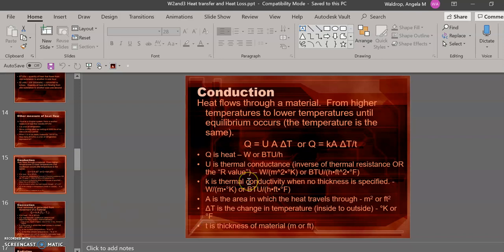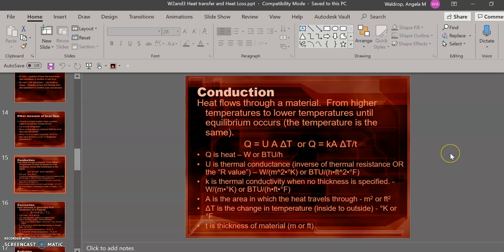For the first mode of heat transfer, conduction, here's the equation needed to do calculations. You will notice that there are two equations here. The first one, Q equals UA delta T, is primarily used for buildings. The other, we will use for smaller conduction calculations. The second is Q equals KA delta T over small t. Q is noted as the heat. U or K is the thermal conductivity. A is the cross-sectional area that the heat must travel through. For example, what is the area of a wall that heat must go through to heat or cool your house? And delta T is the temperature difference. It's basically what you're trying to heat up or cool it down to. Little t is the thickness of the material that the heat travels through.